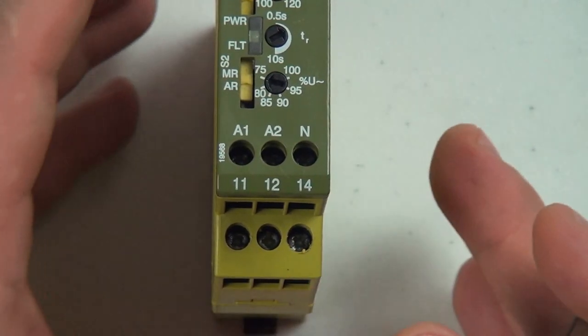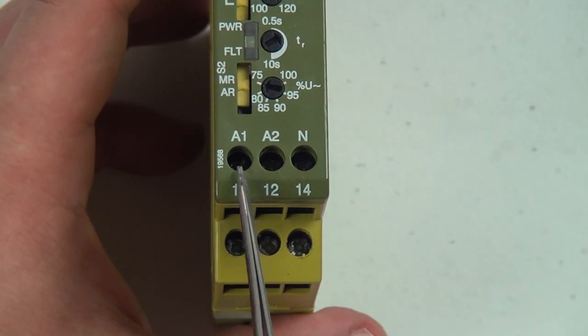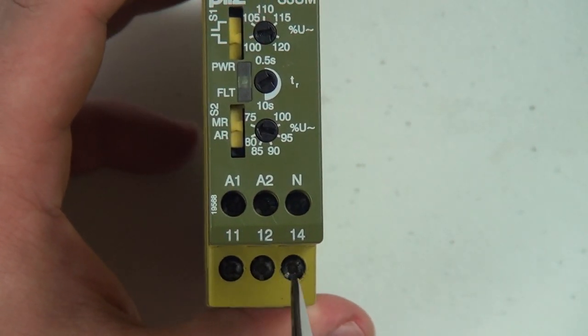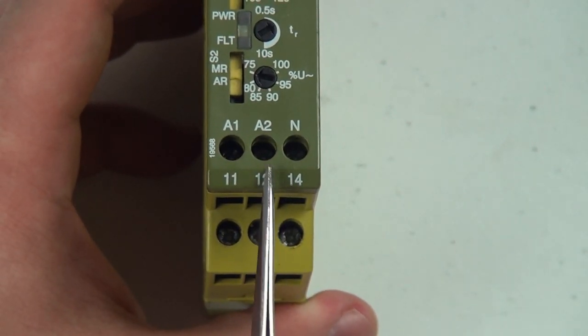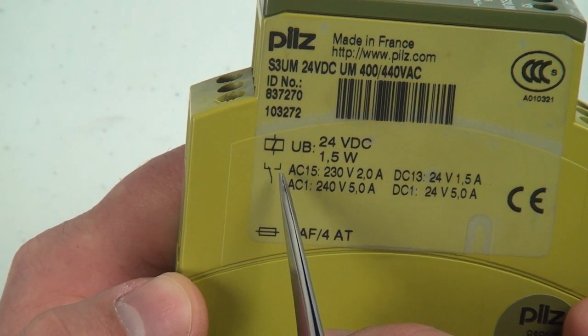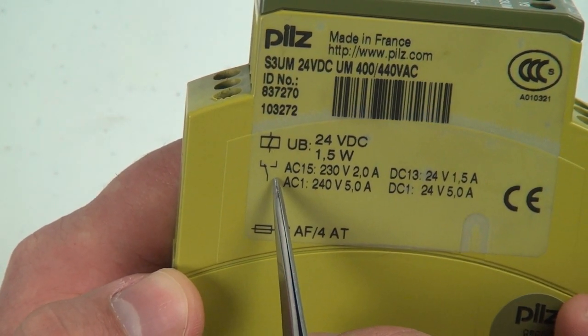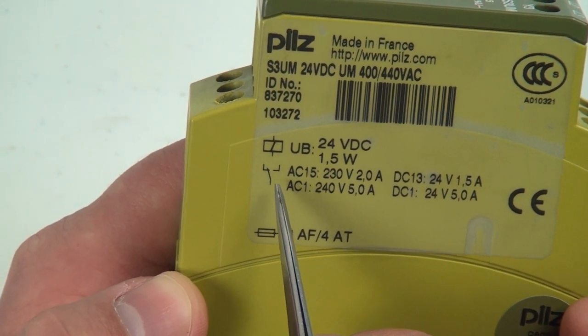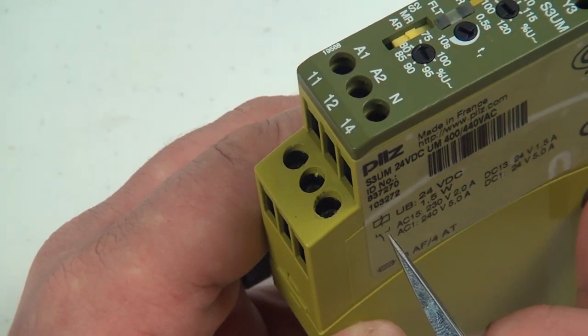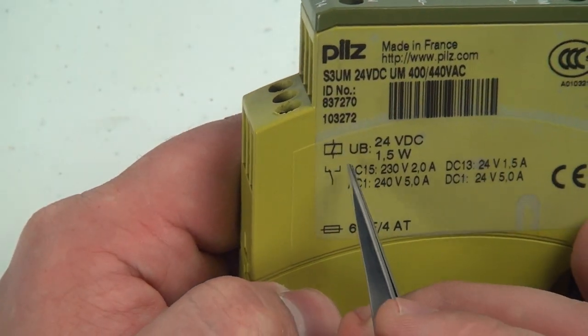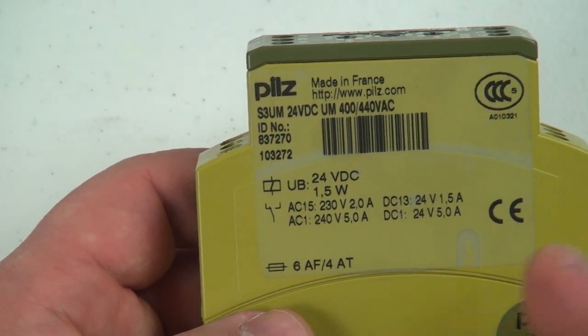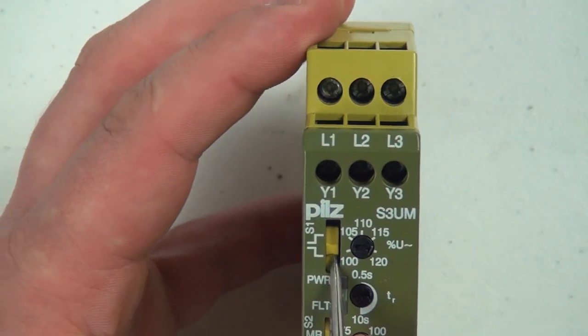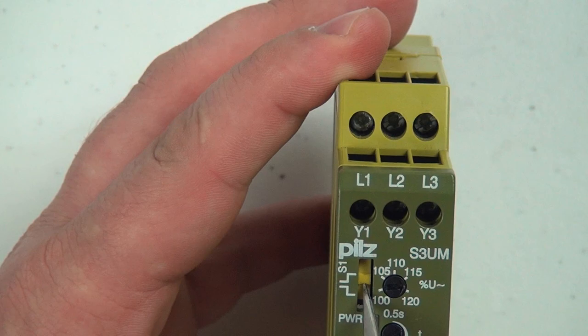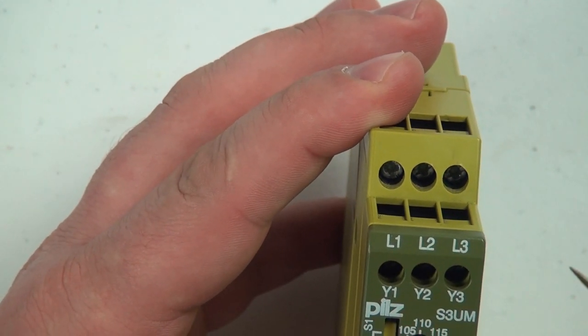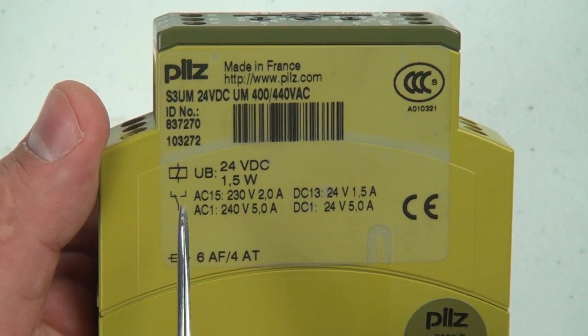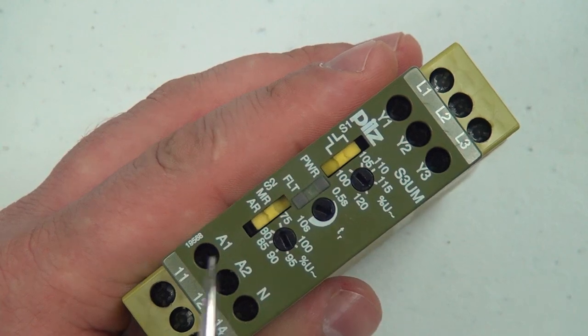These are the internal relay contacts. What they do is 11 is common, and then 12 and 14 are your normally open, normally closed, but I can never remember which one is which. Sometimes they give you a little cheat sheet right here, but apparently this time they didn't, so I still don't know which one is which. I want to say I think 11 is the common, 12 is the normally closed, and 14 is the normally open. And what this switch does right here is when you switch it one way, this relay is normally open. And when you switch it the other way, this relay is normally closed. And basically it modifies what's the faulted state and what's the not faulted state for when the relay has power.